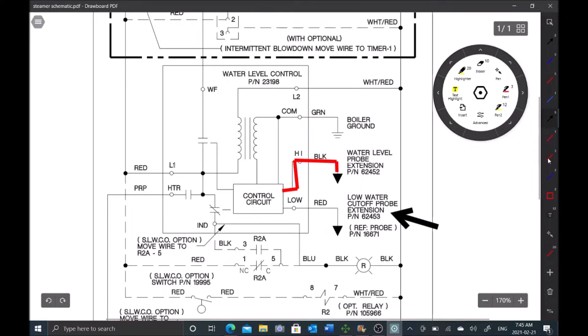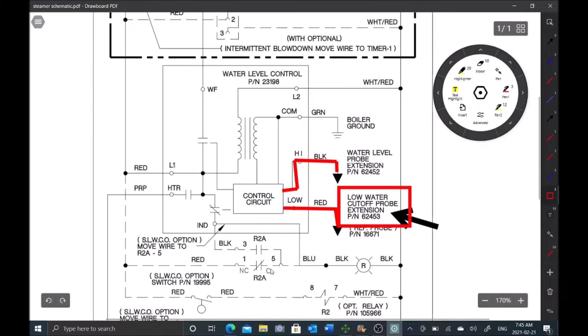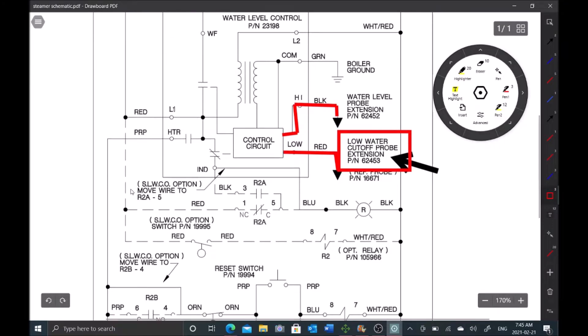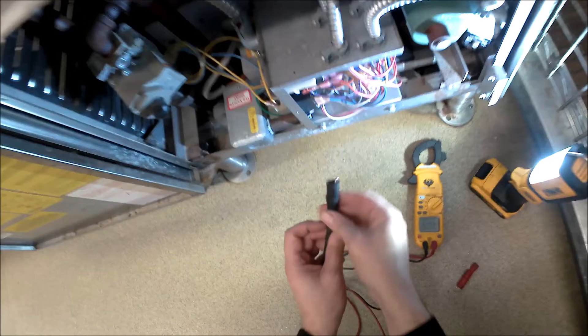The next thing we tested is this low water cutoff probe. Very simple test - you saw that red LED on the board. As soon as I disconnected that wire, the red LED came off. That tells me this low water cutoff is good. Now we can move on to testing the secondary low water cutoff switch.